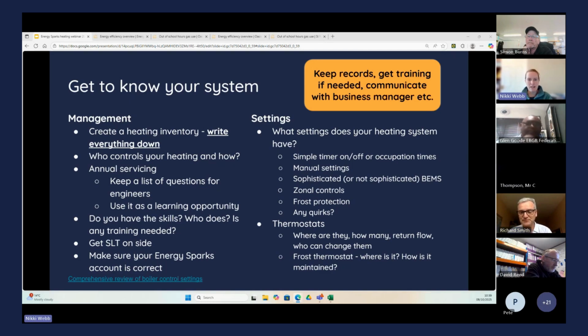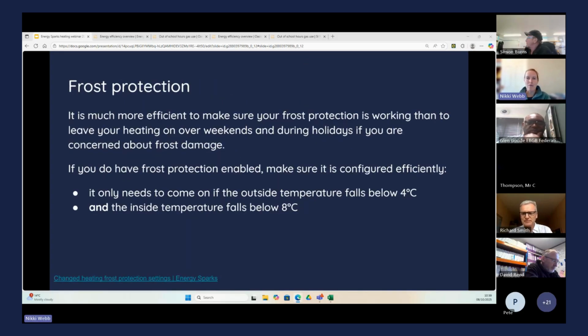Thank you. I've already mentioned frost protection, but it's important to get right. It's more efficient to have the frost protection settings set so the boiler only comes on if frost damage is likely, rather than leaving the heating on all weekend. Some people will be more conservative and worried about frost, but generally these are relatively conservative settings: an outside temperature of 4 degrees, so if it goes below 4 your heating comes on, or indoors of 8.